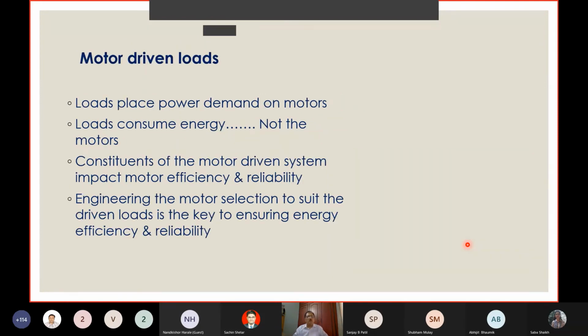Similarly, what about the loads? Loads place power demand on motors. So it is the load which is responsible for consuming energy. So when you do an energy audit, don't say motors are consuming energy. Say the motor is delivering the energy demanded by the load, and therefore whatever energy saving that we are going to attempt will have to be in the total system, not just the motor.